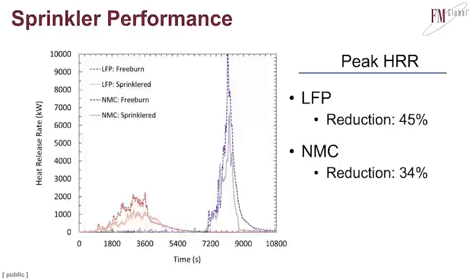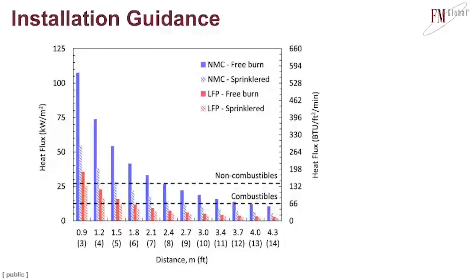The number one way to reduce the hazard to the surroundings, the simplest way, would be to just move things far enough away so that they aren't exposed to the fire anymore. And if I'm going to do an analysis, I want to do it when the fire is at its peak, as in it's providing its peak exposure to the surroundings. And heat release rate, HRR, by the way, is the amount of energy the fire is releasing. So if I take that peak heat release rate number, I can develop this type of graph.